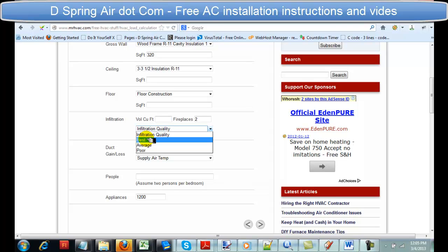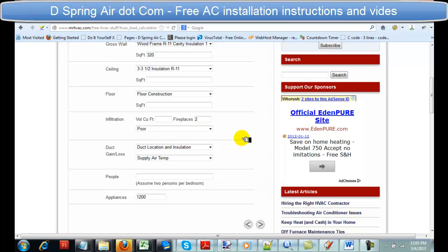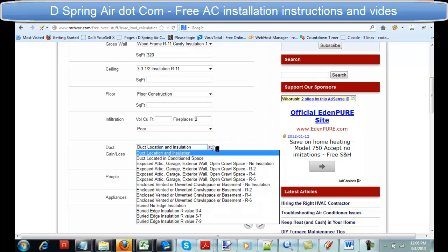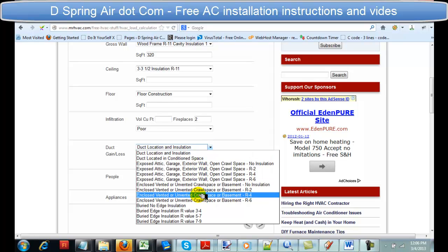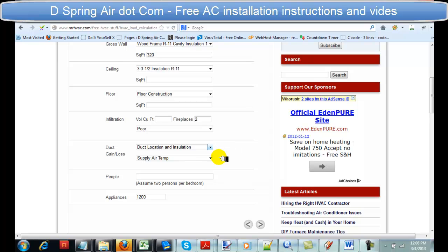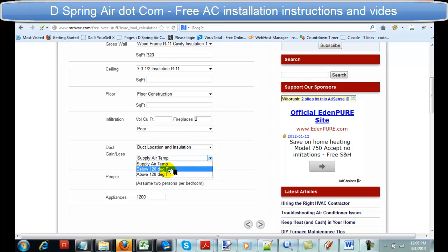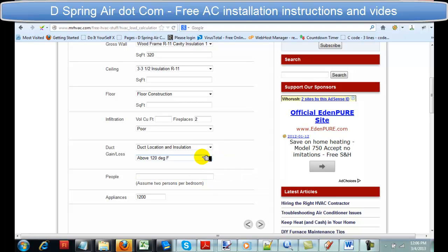Infiltration quality: if your home is relatively new with two-by-six walls and thick insulation, it's probably very good. Average would be homes from the seventies to mid-nineties. Poor would be homes built before the seventies. Duct location and insulation is self-explanatory — some ductwork has insulation, some does not. Supply air temperature is mostly for heat loss: below 120°F would be a newer high-efficiency furnace; above 120°F would be an older 80% furnace. You can test it by sticking a meat thermometer through the ductwork while the furnace runs.